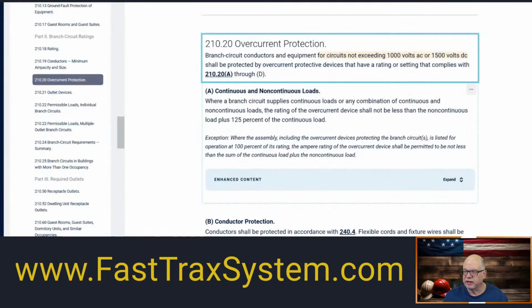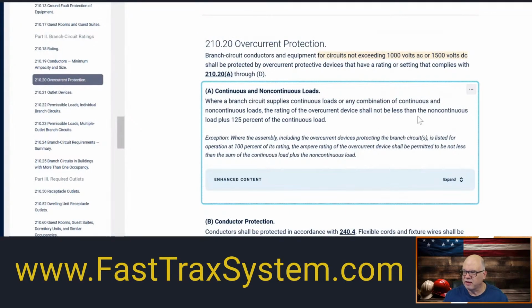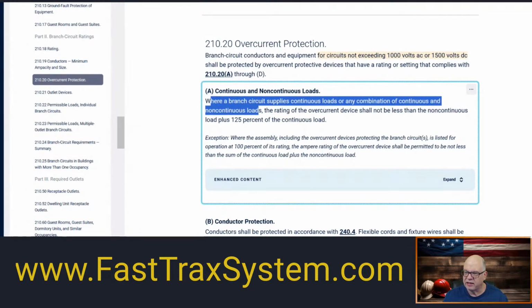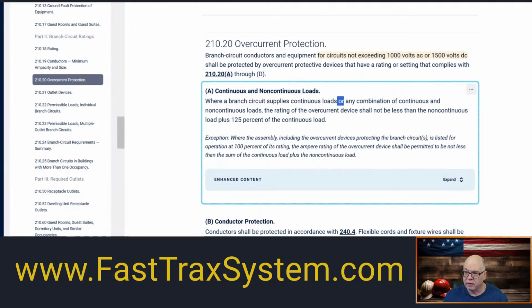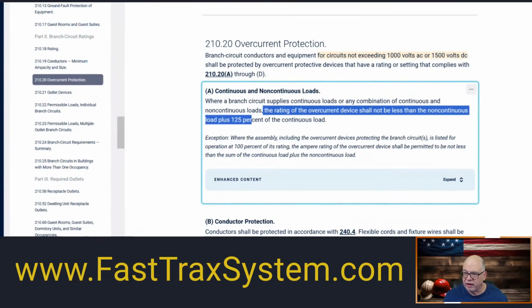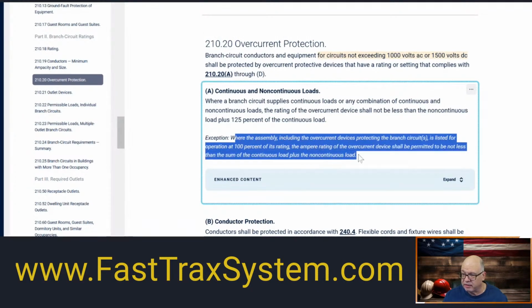Okay, so for continuous loads, again, it says not less than the branch circuit supplying continuous loads or any combination of continuous and non-continuous loads. So there's an "or" in there. That "or" is telling me that if it's continuous loads or a combination of non and continuous loads, either way, the rating of the overcurrent device shall not be less than the non-continuous load plus 125% of the continuous load. Okay, so we've got nothing in here about additional ratings or 100% rating of the fuse.